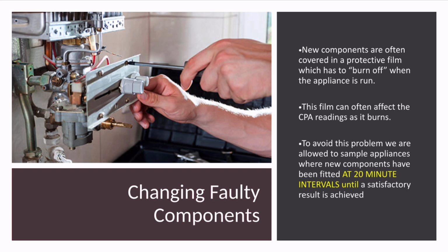We're aware of that, or the people that make the rules around gas are aware of that because it's happened. And they say that to avoid this problem, we're allowed to sample appliances where new components have been fitted, and only in that case, where new components have been fitted, we can sample them at 20-minute intervals. So that's sample them every 20 minutes until you reach a satisfactory reading. So you've put something new in, you fired it up, you do your reading, and your reading's way out. You're allowed then to wait for 20 minutes and then do it again. If the reading's still out, you can wait 20 minutes and do it again until the reading normalizes. And please remember, you can only do that where a new component has been fitted.